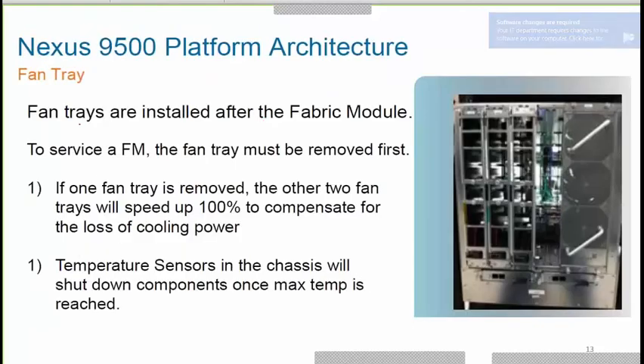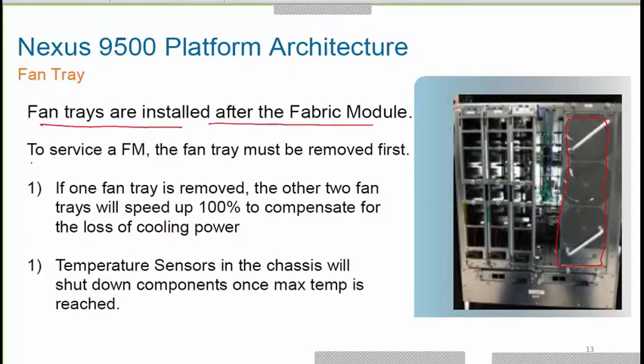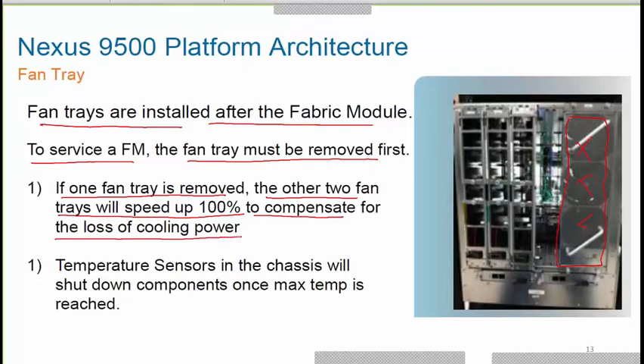The fan trays are installed behind the fabric modules. To service a fabric module, you first remove the fan tray, then remove the fabric module, replace it, and reinsert. If one fan tray is removed, the other two fan trays will speed up to 100 percent to compensate for the loss of cooling. Temperature sensors in the chassis will shut down components once maximum temperature is reached.